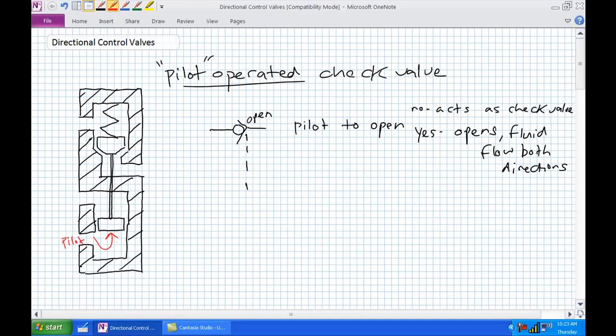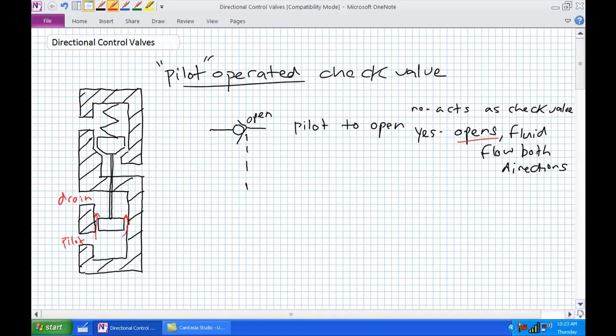If there is pilot pressure, it's pushing on the piston, which is connected via a rod to the poppet, and pushes it open — now you've got fluid flow in both directions. The poppet moves back and allows flow both ways. There's also a drain passageway in the plunger because if pressurized fluid from the pilot port comes back there, it would be hard for the plunger to activate. You may see the drain symbol on the schematic.